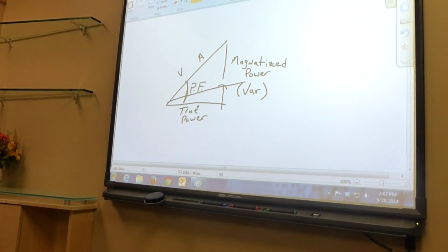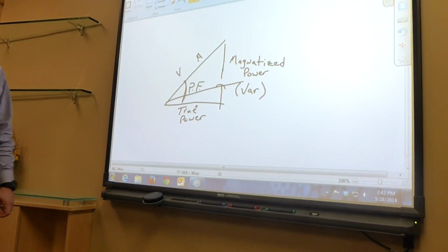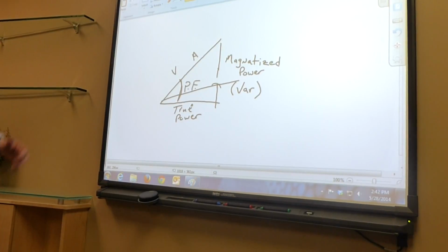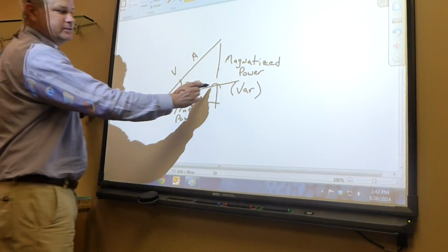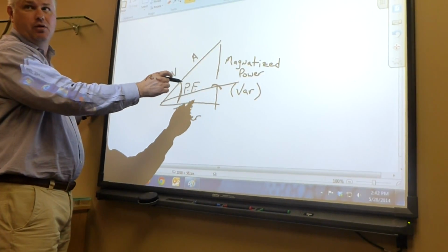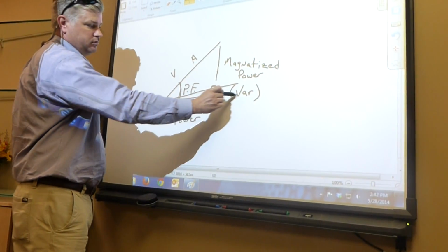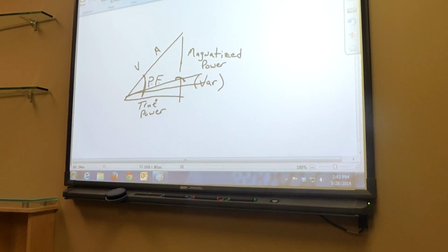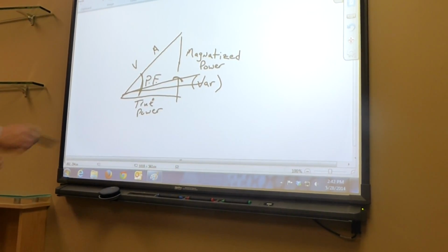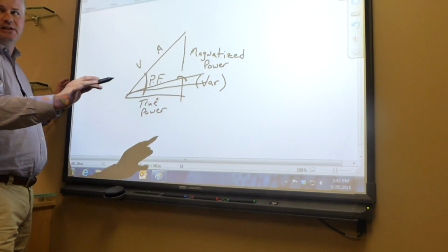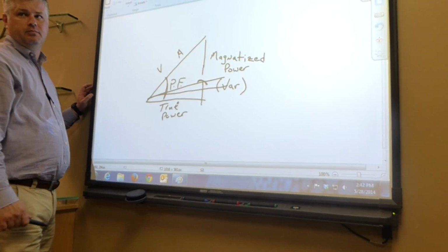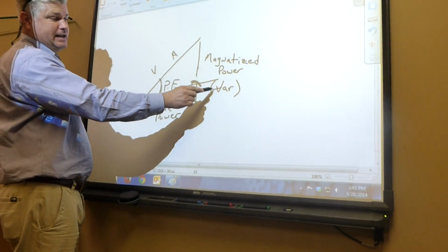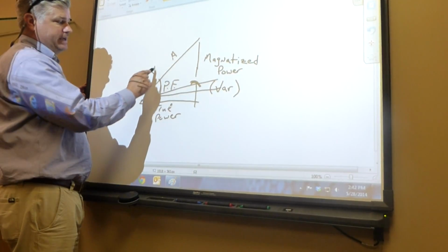We're analyzing the capability of that panel by taking total breaker amps. Okay. And then we have assumptions in our formula to determine how much capacitance we need to add to that panel to lower this angle. And the capacitance is the capacitor bank? Yeah, capacitor banks. But what we want to do with this, we can take those assumptions out.